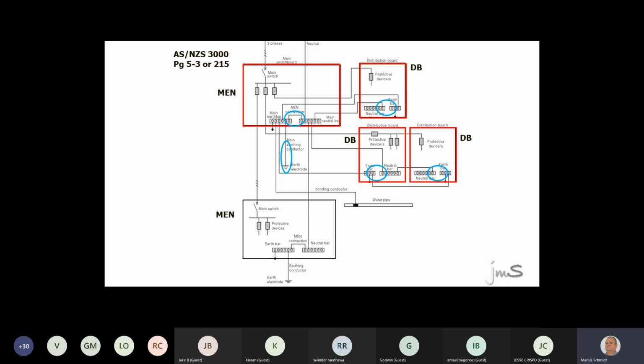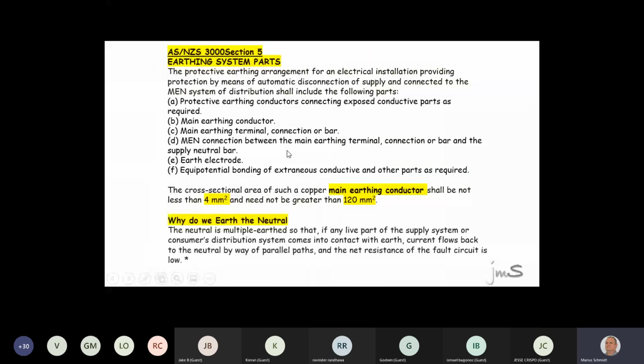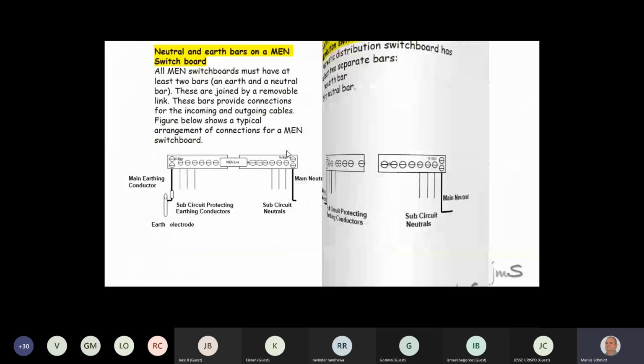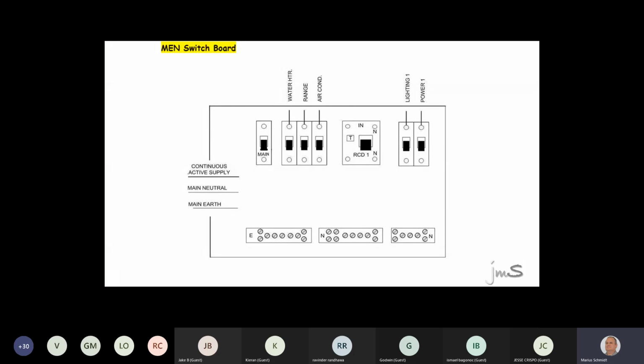That's it. We only have 3 earths. There's no other earths in this country. Oh, by the way, there is one, but we're not working with that a lot. We call it a functional earth. Right. And last thing I'd like to share, your main earth wire and your bonding wire must be a wire which runs by itself. You can't have it inside a cable with other active conductors. You guys with that? Right. From your earth peg, correct. Because your main earth wire is an extended earth bar. Yeah, well, sometimes you see pipes on the stairs sometimes. Yes. Now, the law changed in 2003, where you can extend the wire from where the clamp is to a water pipe. That's all it says now.